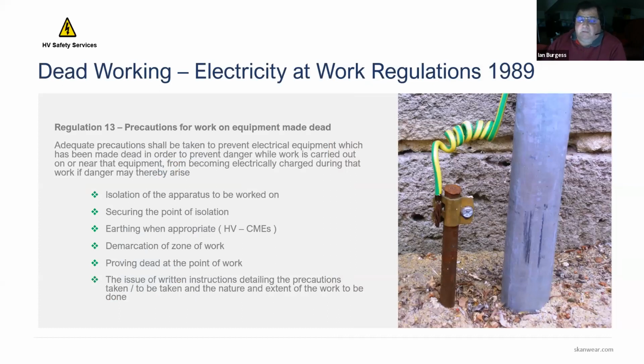So dead working. Now this is back to the Electricity at Work regulations. These statements are the law as far as we're concerned in the UK, and you can't break them. They will expect the isolation equipment to be worked on, securing that point of isolation, earthing if appropriate, HV, creating a zone of work, proving dead at the point of work, and it tells you how to do that. Well, the guidance recommends how to do it, rather. And then the issue of a written instruction detailing precautions taken.